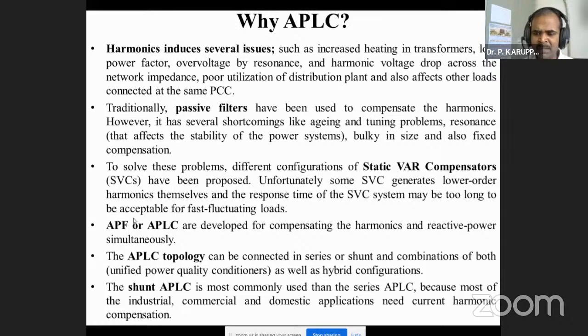Harmonics also affect the other loads connected at the same point of common coupling. Suppose in one house they are running some oil mills, as well as our home appliances, and there are many houses. Some houses may have a rice mill that does not have three phases, so many motors are running on a single phase, and they are connected to the same transformer that supplies the home appliances. Even coconut oil or other oil machines are single phase machines and are connected there. Because of that type of load on the same line, our home load may be affected. That is the point: it will affect the other loads connected at the same point of common coupling.